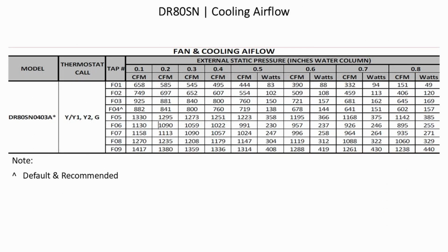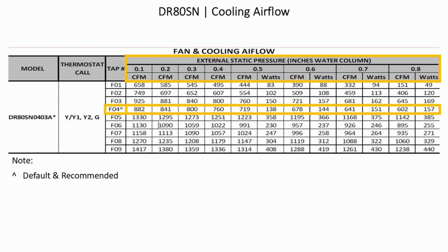DR80SN cooling airflow. On the chart below, for fan and cooling airflow, I've highlighted the external static pressure in inches of water column from 0.1 to 0.8 inches. Below that on the chart, you will see the CFM at that static pressure and the watts of power used at that static pressure. I've highlighted the F04 tap, which is the default and recommended fan speed for the furnace listed. I've done this to give a better idea of the correlation between CFM, wattage, and external static pressure. You'll notice that as the ESP increases, the CFM goes down and the watts of power used increases.